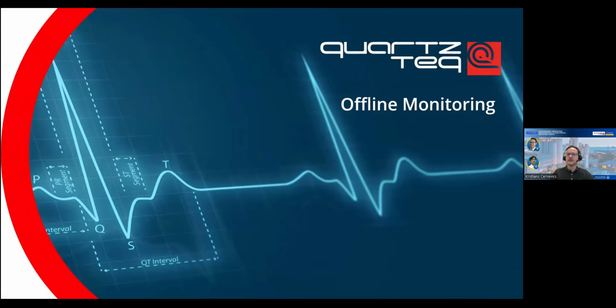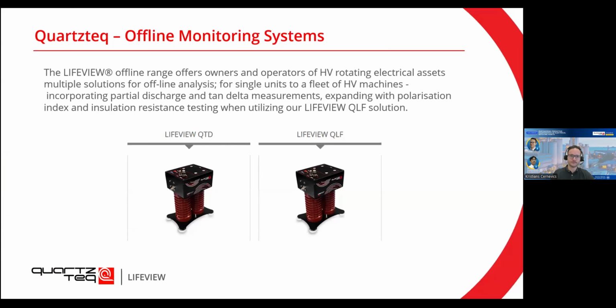Then quickly about offline monitoring. To remind you, offline monitoring would happen when the machine is switched off. So you would need a different tool. What we offer here is two types of tools, the LIFEVIEW QTD and QLF. This can be used as well for multiple machines. No sensors would need to be installed previously. It also incorporates some additional parameters to be measured, such as the tan delta, the polarization index, and insulation resistance. And yeah, this would also be a portable tool that you could carry for multiple machines to test them.